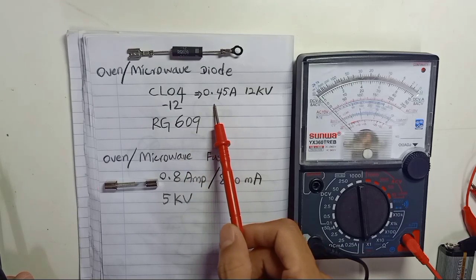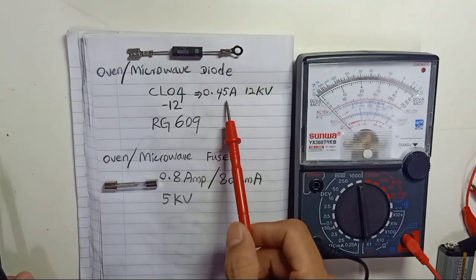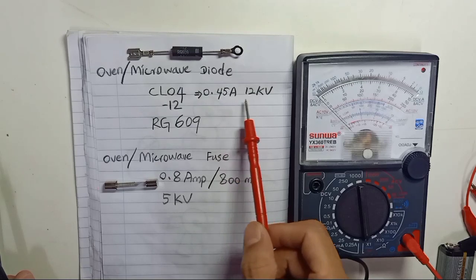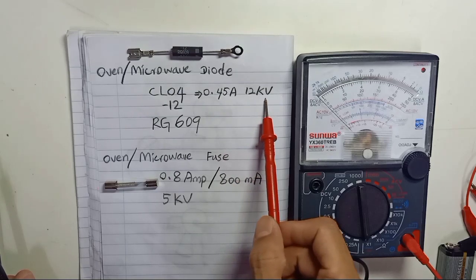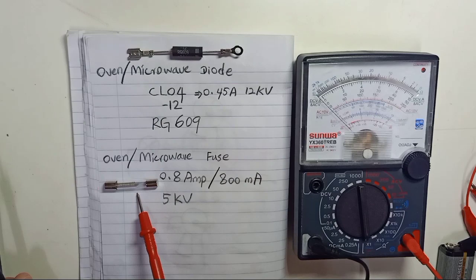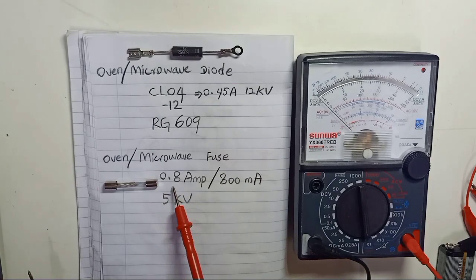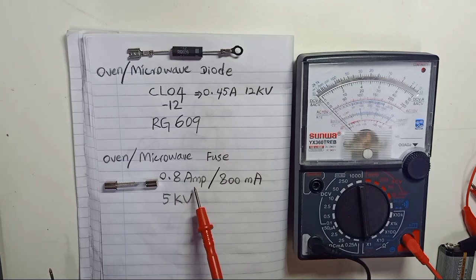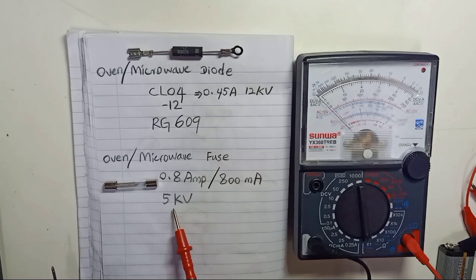According to the data sheet, this diode is rated 0.45 ampere at 12 kV. And here is the fuse, a very common type, rated 0.8 ampere, which is 800 milliamps, at 5 kV, which means 5000 volts.